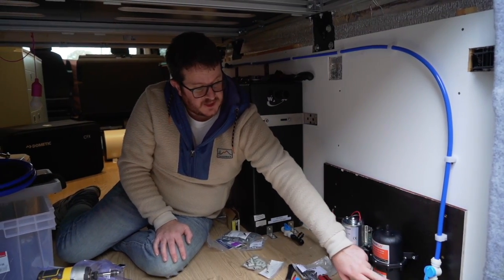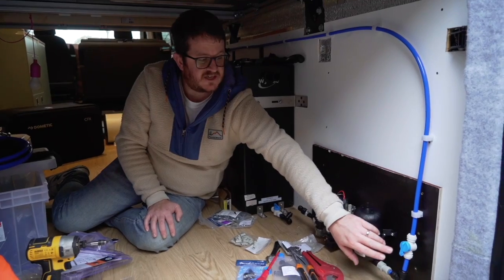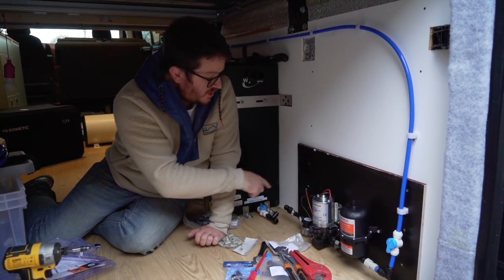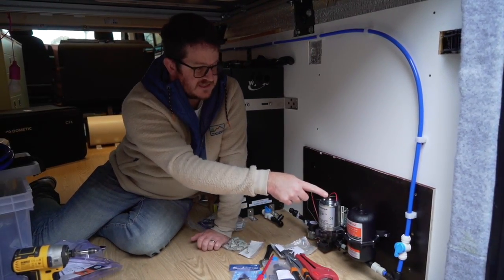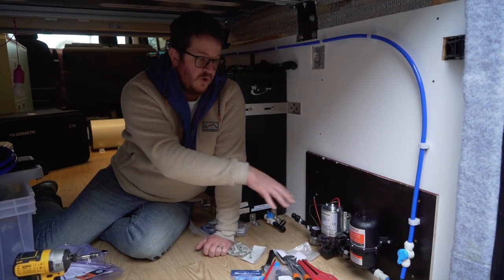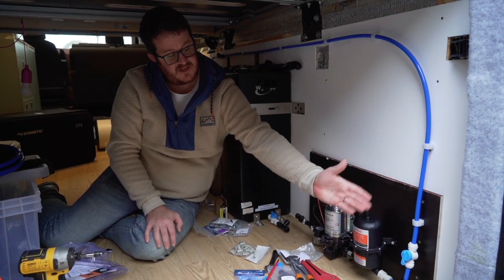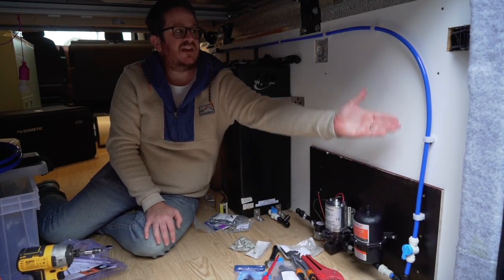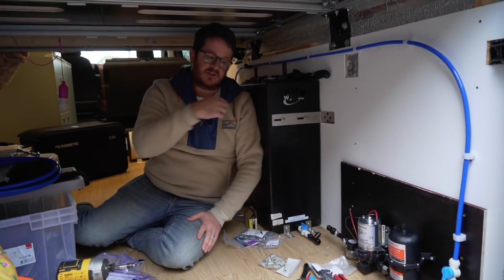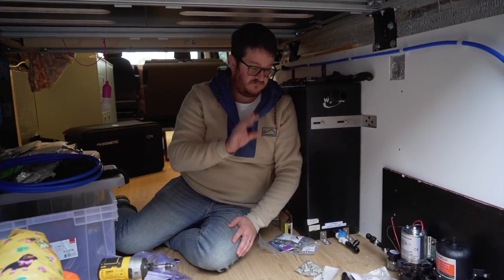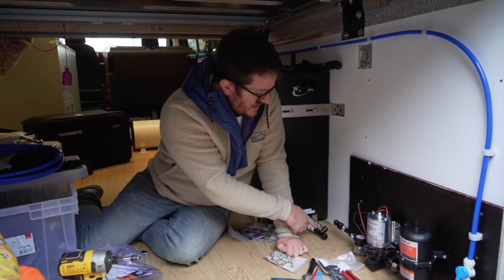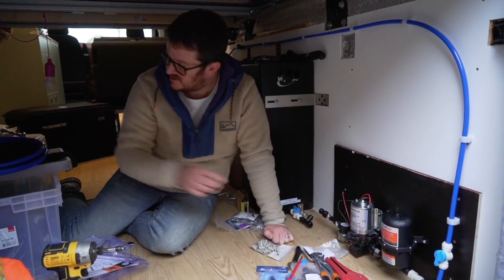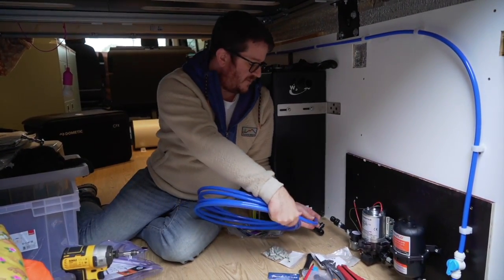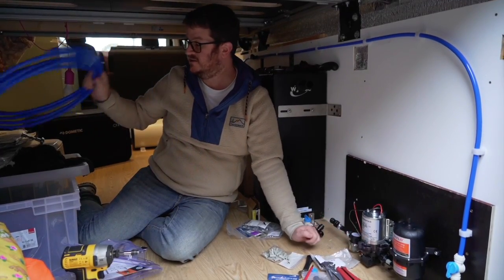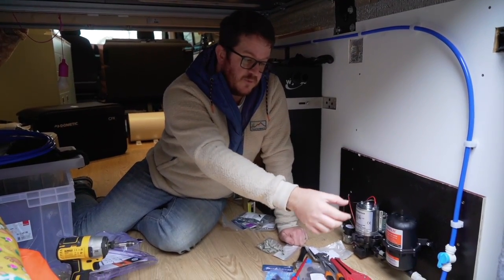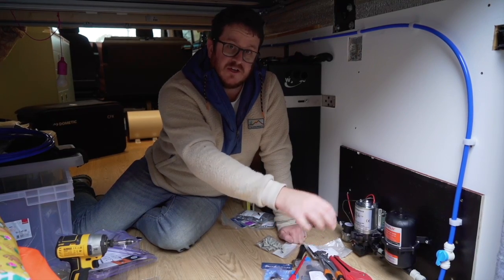From the accumulator it goes up through another isolator. I put another isolator in just so if I want to work on any of this, I can isolate here, isolate there, and work on these two pumps. If the isolator isn't turned off, the water will carry on up along the top here and go off to our water system, which we'll look at in a minute. The reason I've put a T in here is because there will be a piece of pipe at the end that runs parallel to this, with a drain plug on the outside.